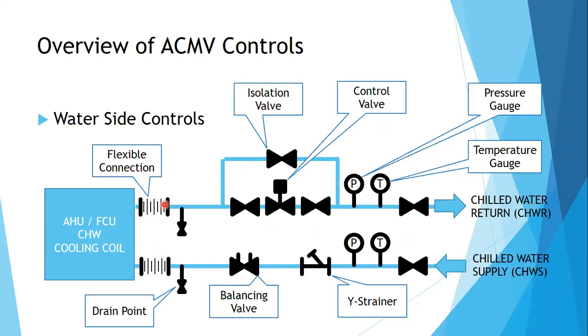This is a flexible connection. For your valve assembly, you need a flexible connector, so that the vibration from your air handling unit and fan coil unit will not transfer to your piping system. Remember, your air handling unit has a fan. This fan is vibrating when it's in operation. So you don't want this vibration to transfer to your rigid pipes. These pipes are rigid and they are installed and fixed. You don't want vibration to be going through them or else your installation will get loose. So you put a flexible connector so that the vibration is isolated.